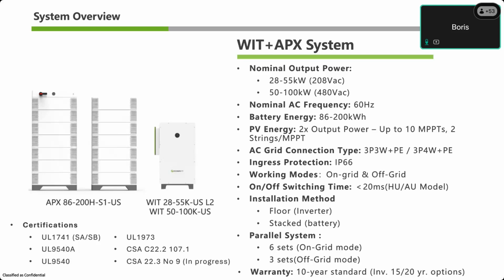They can be paralleled. If it's a system that is entirely on grid and there's no need for any backup, you can do up to 6 in parallel. And if there's any off-grid, any backup protection UPS loads, those can be paralleled up to 3. So we have 3 for maximum off-grid loads.